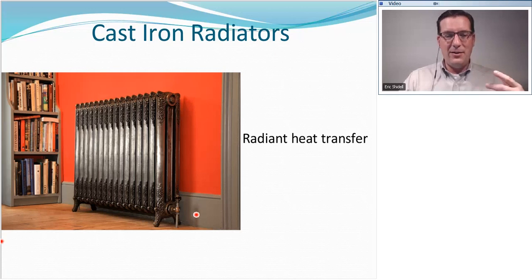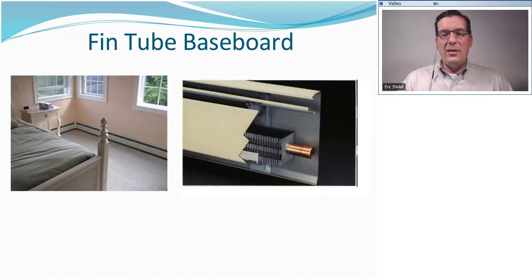They're optional. So here we have a copper tube with aluminum fins around it, encased in a metal shroud with an opening on the bottom and an opening on the top. Cool air falls to the floor, comes in contact with the hot element, and rises up and through. And this is what we call natural convection. These are what we call convectors. And I'm going to write this down on the bottom here. I want you to do the same.